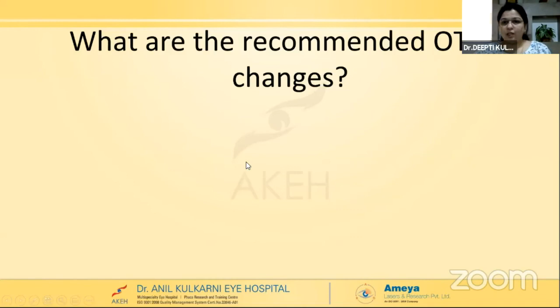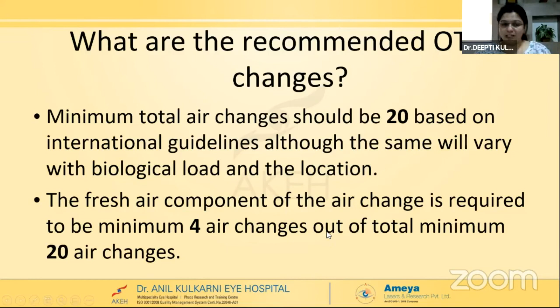This is probably the last question. What are the recommended OT air changes? Ma'am has clearly said that we need a minimum of 20 total air changes, of which 4 should be fresh air exchanges.